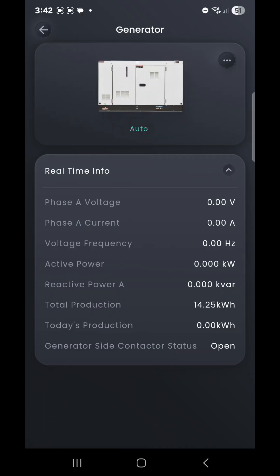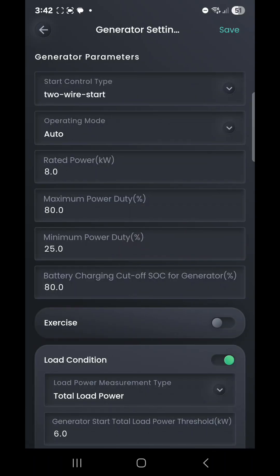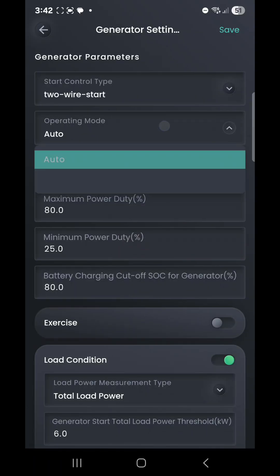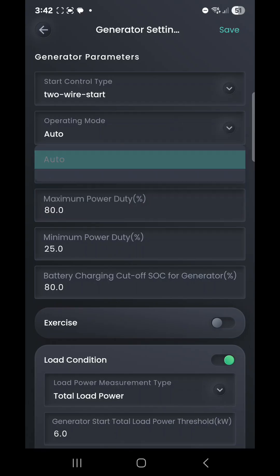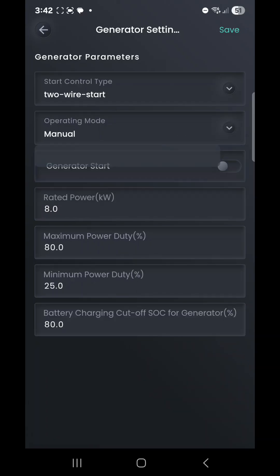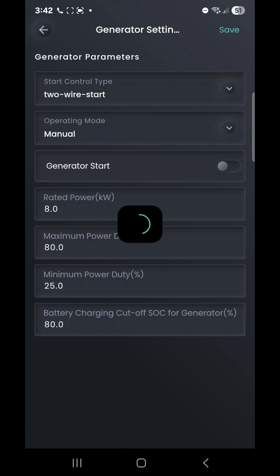If you wanted to override that and force charge your battery system so you can run it during a time where it's not going to be an annoyance, we can simply go to the top three dots on the right-hand side. Click on that, it's currently on two-wire start. We can see operational mode, which is the second drop-down menu. If we click on operational mode, we can change that from auto to manual operation, and it's essential that we press Save on the top right-hand side.